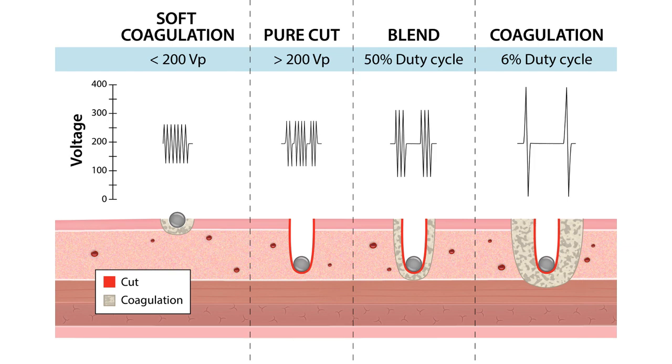Blend current has 50% duty cycle. A coagulation current has 6% duty cycle. That means with that 6% duty cycle, there is high voltage and then a lot more inactivity before the next cycle starts. And that inactivity would allow the coagulation to happen.